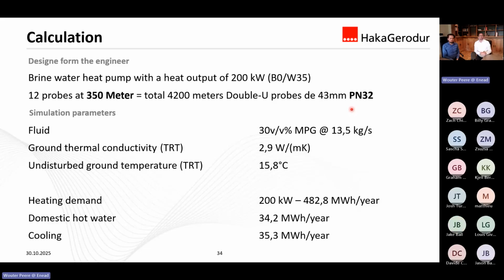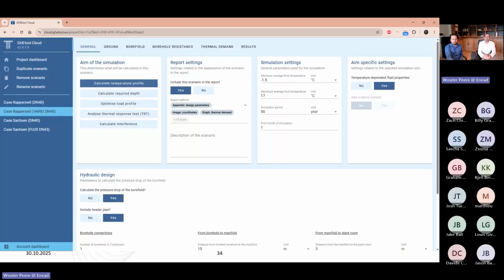So here we have, as mentioned before, 12 probes at 350 meters, so a total of 4,200 meter probes, DN43 PN32. The fluid is also a brine, and the ground thermal conductivity is 3 watts. The average temperature in the ground is 15.8 degrees Celsius. So now we put all these figures into GHEtool, and let's see what comes out of it.